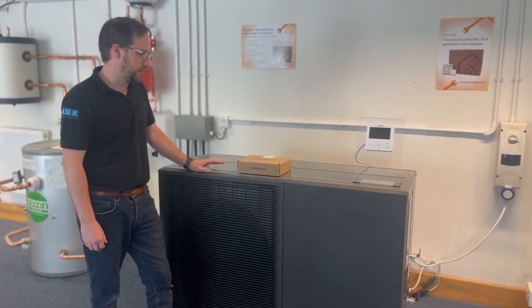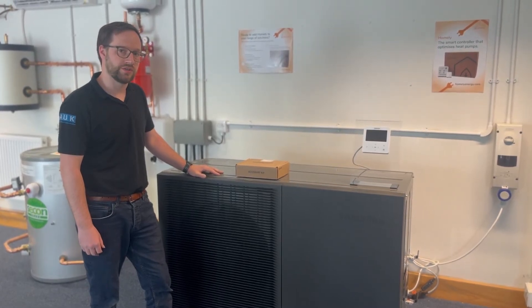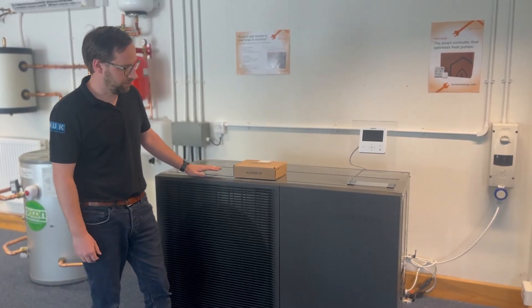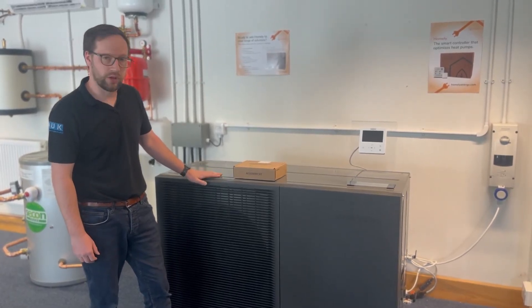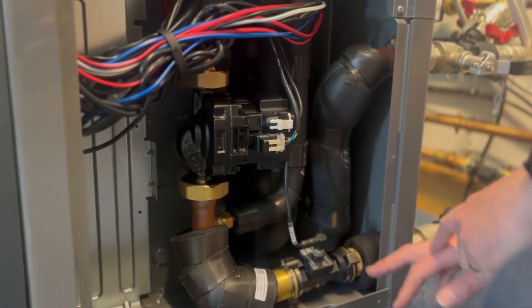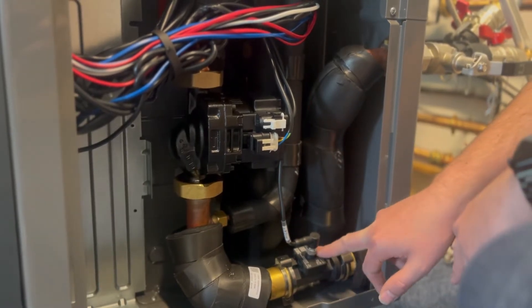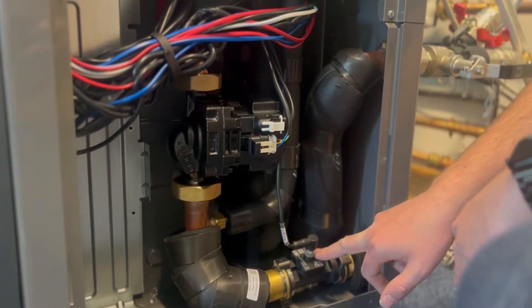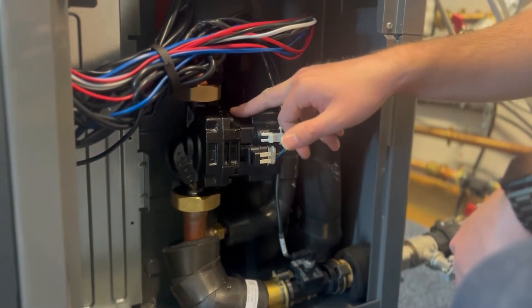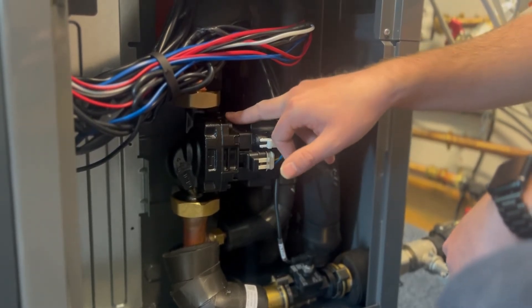There are a couple of key differences in the integrated hydro unit compared to Samsung's other EHS heat pumps. A lot of the hydraulic components are contained within the monoblock. As this is the integrated hydro unit, within this unit you'll find the flow sensor and the circulation pump. On the smaller units this is a seven and a half metre head pump; on the larger units it's a nine metre head pump.